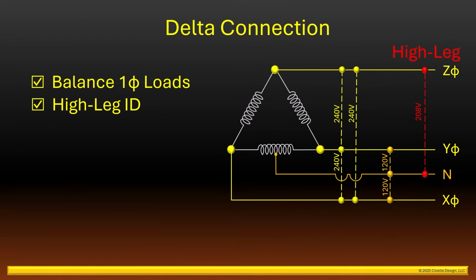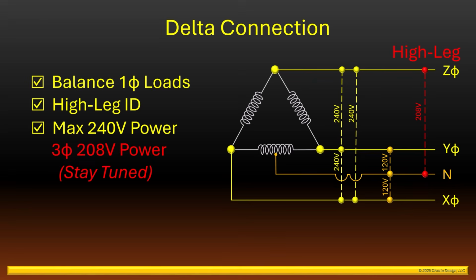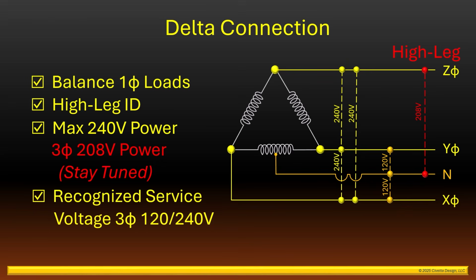Also, the individual transformers that make up this bank are rated to provide 240 volt power, and this configuration utilizes that to produce the maximum possible three-phase 240 volt power. We'll contrast that in the next video, where we'll show how these same transformers are used to provide three-phase 208 volt power. Although beneficial, the 208 volt configuration does not utilize the full voltage capability of these transformers like this one does. And finally, this is usually recognized as a three-phase 120 240 volt service. The 208 volt, although present, is not typically recognized by the utility as one of the service voltages.